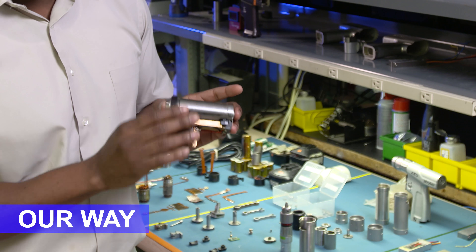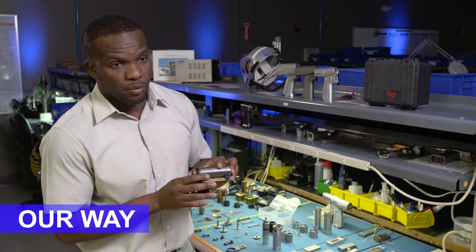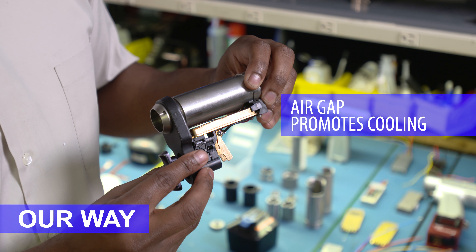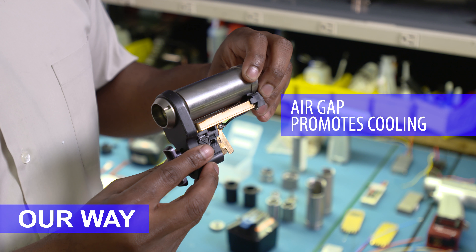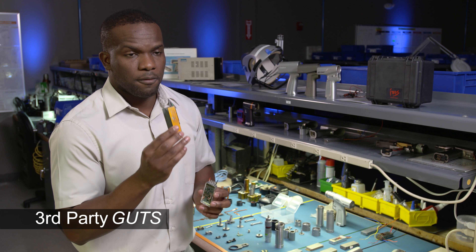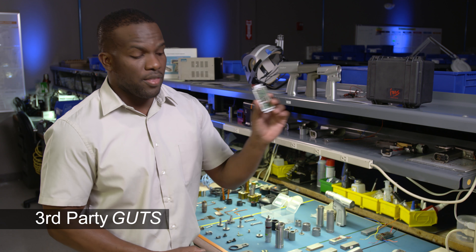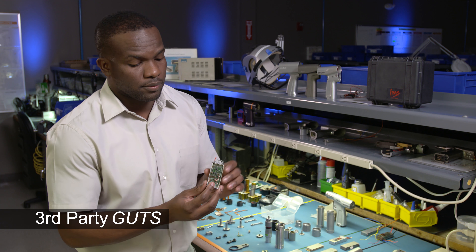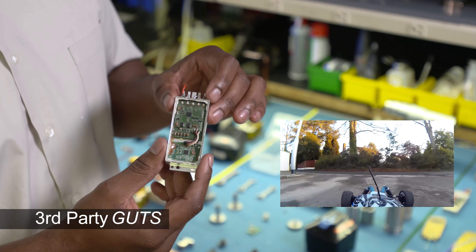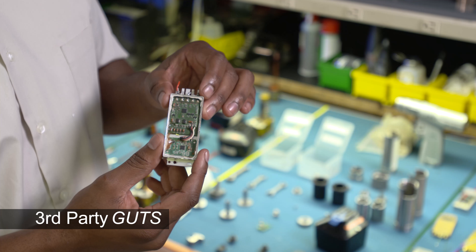This is a 4200 that was serviced by IMS. The difference between this and the other third party is that if you look here, you'll see an air gap. The controller operates at a certain temperature, and with this air gap it keeps it within that range. These are the two most common third-party controllers — one is an electronic component sourced online, and another is from a Canadian company that buys RC toy cars, takes the circuitry out, and puts it into the device just to get the drill rotating and ship it back out.